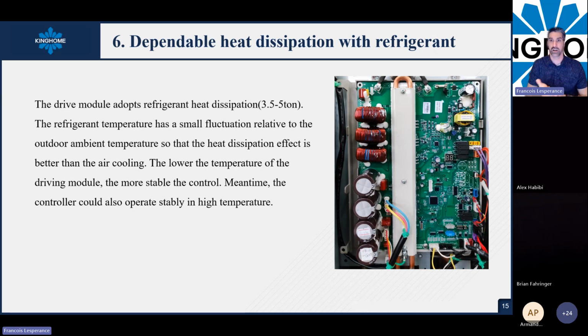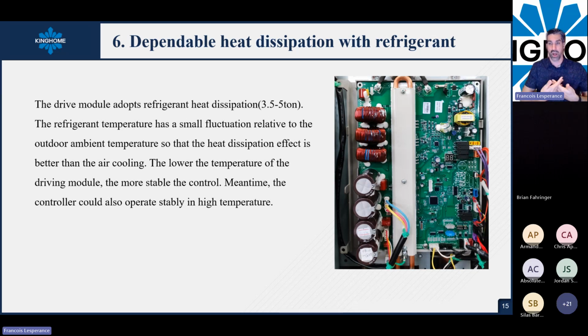Also, we have a different kind of heat dissipation with the refrigerant. We will use a liquid cool dissipation process for the 3.5 ton to 5 ton units. This is what it looks like. On the board directly, you will have the liquid line, and this board is installed vertically. So you will not have water or condensation dripping on the board directly, because it's not in a horizontal position, it's in a vertical position. Then the liquid line just goes through here and removes the heat from the processor and all the boards, the heat coming out from the board here. So that's the liquid cool application.